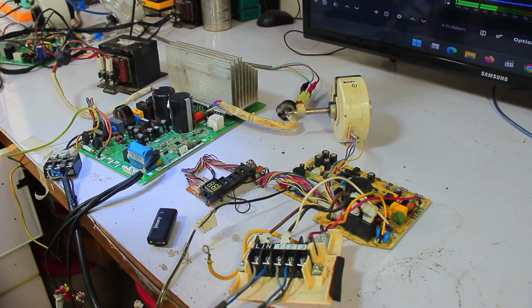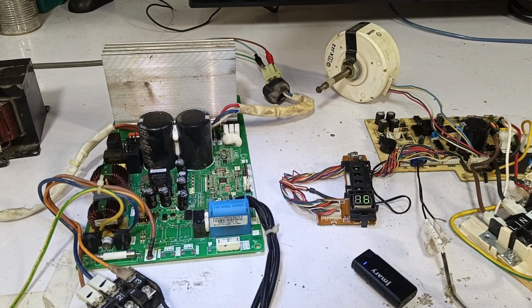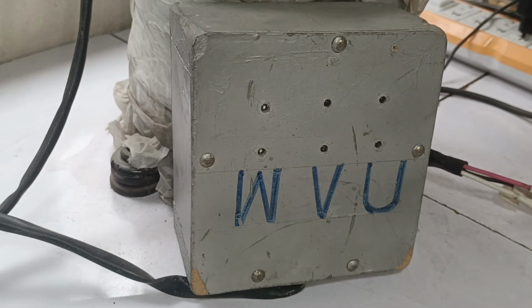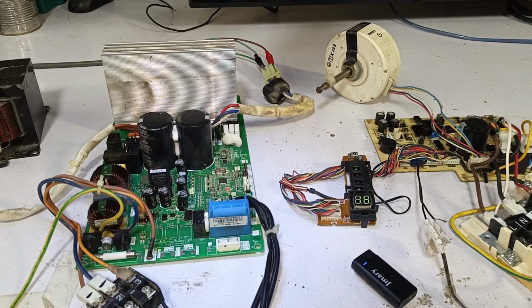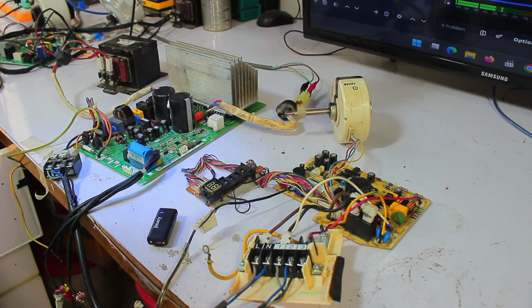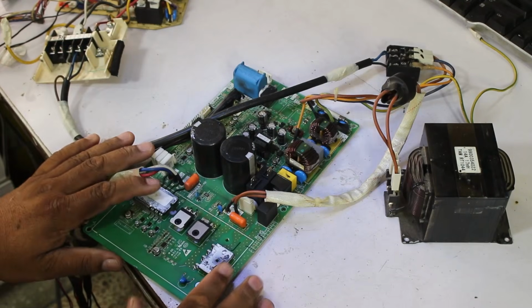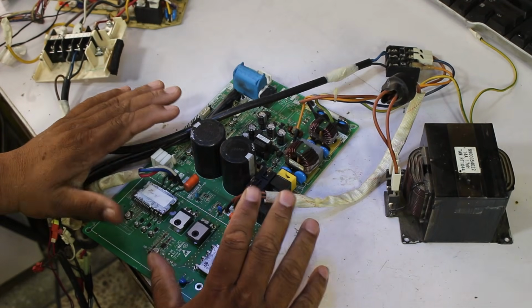Now, during testing, as soon as I connected the system here, it was not starting the compressor. When the compressor did not start, I tried to get an error code from the system so that the work I need to do here would become easier. But the error code was also not appearing quickly. So I left the system running for 2 to 3 hours, thinking that maybe at some point it would show an error. Now I have tested its indoor and outdoor units very well, and I did not find any kind of fault in it.